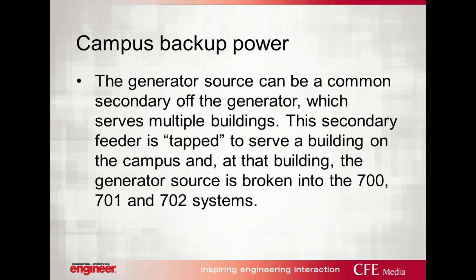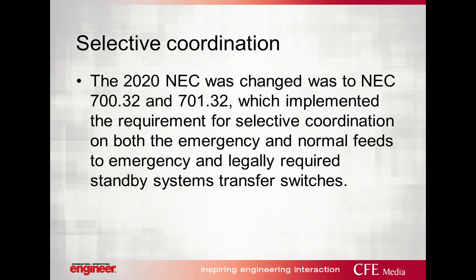So if I put in a normal distribution loop, I may back up that normal distribution loop, but guess what? That power that's feeding off of that loop may or may not be deemed as 700, depending on the authority of jurisdiction applicable. I may have to have a separate distribution feed from my generator system out to the buildings, each one of those buildings having a separate transfer switch to be fed off their normal power, which is a separate feed distribution. To pick it up. And I can feed 700, 701, 702 off of that, more or less tapping the feeders.